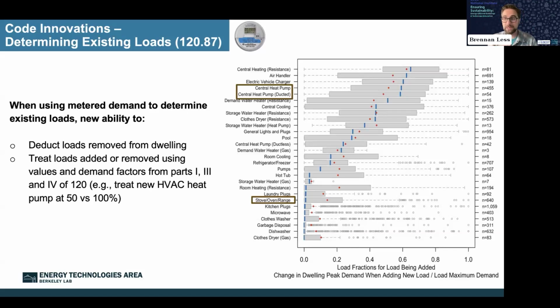I think we've made some big changes here. For starters, when using this metered demand method, you're now able to deduct loads that are being removed - say you're removing an air conditioner and replacing it with a heat pump. Seems logical you should be able to deduct the one and add the other, but that wasn't the case previously. Now we can treat the loads we're adding or removing using values and demand factors from elsewhere in the load calculations section.